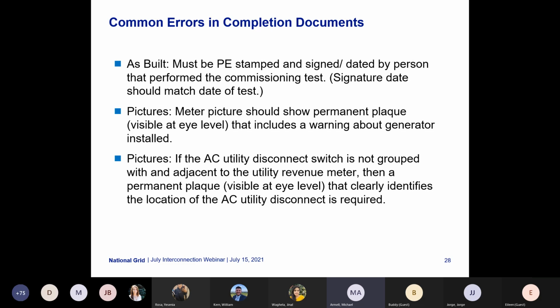So on the existing, if it's a behind the meter system and we have an existing meter that we're going to exchange, it should be noted that there's a placard that this is a dual power source. And on that Mass Save production meter, we want it noted that it's a production meter, as well as the AC disconnect switch. If these are not near each other, we want that placard to also describe the location of them so that they can be found by National Grid as well as anyone else who has to access, whether it was a first responder, et cetera. Next slide.